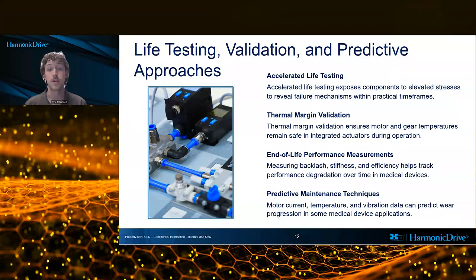The best way to ensure those critical requirements, though, is through robust testing and validation, both on the customer side and at Harmonic Drive. Life testing and validation are central to demonstrating the reliability of medical servo systems. Accelerated life testing is commonly used to expose components to elevated loads, temperatures, or duty cycles to reveal potential failure mechanisms within a more reasonable time frame. But it's essential that these tests accurately reflect real-world operating conditions, as unrealistic acceleration can produce failure modes that you're not actually going to see in real life.